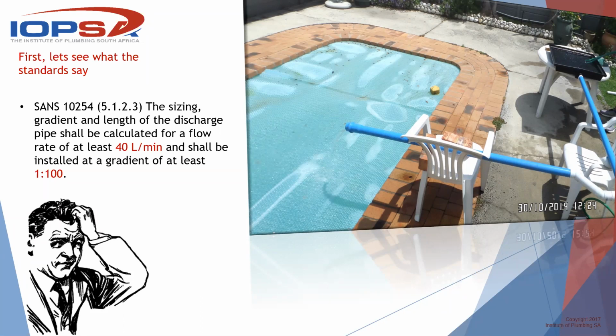They don't give us anything else. They don't say to us, it must be 50, it may not have more than 2 bends, and it's got to be less than 3 meters. It says you've got to make sure that it can discharge at 40 liters per minute and that it has a gradient of at least 1 in 100. So if it's more, that's great, but it cannot be less. So those are the two criteria that SANS 10254 gives us in terms of the installation of drip trays.